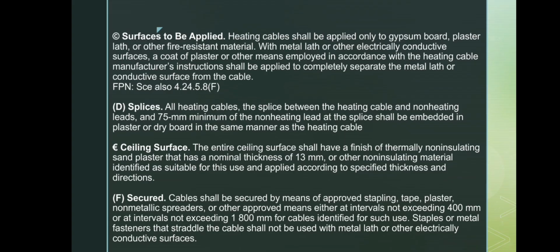Cables must be properly secured using approved staples, tape, plaster, or spreaders. If using regular cable, supports must be spaced every 400 mm. If using cable rated for long spans, supports may be up to 1,800 millimeters apart. Metal staples must not be used on electrically conductive surfaces.